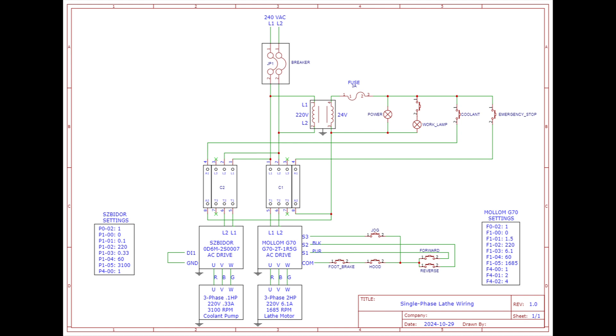To the right of the Mollom G70, there's a jog switch on the front panel, a foot brake switch, and a hood switch. Those are wired in series so that the jog switch, the forward switch, and the reverse switch for the chuck will not operate unless the foot brake is in its normally closed position when it's up and the hood switch is also closed. So those protections remain - the chuck can't be jogged or put into forward or reverse speed unless those circuits are closed.